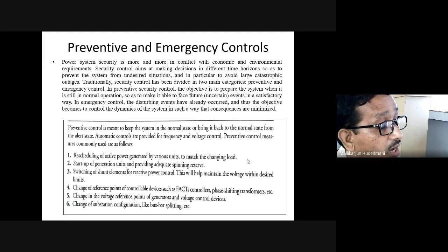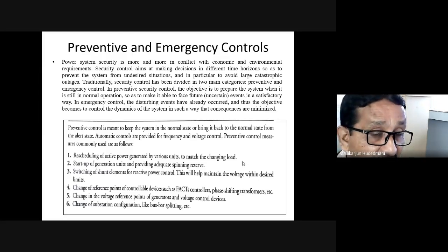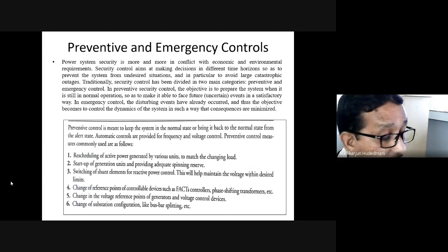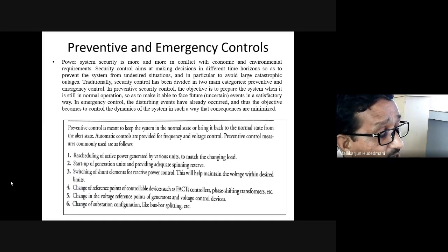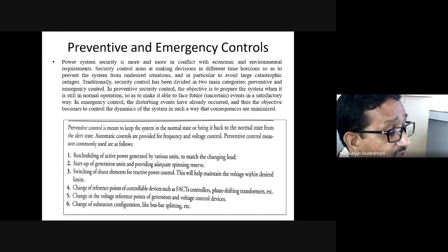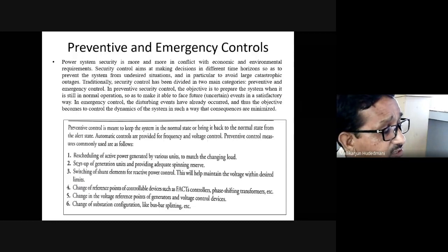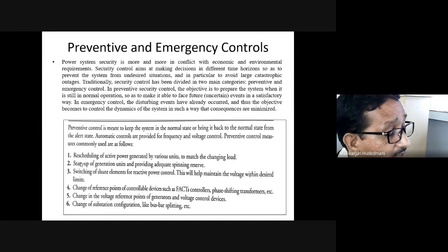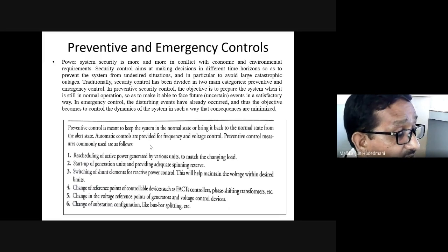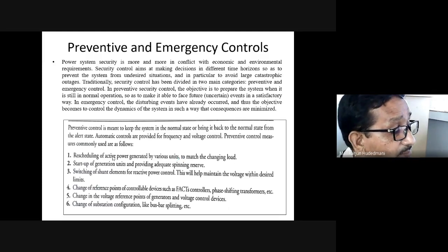Some of the activities are like rescheduling of active power generated by various units to match the changing load. How does the system enter the alert state from the normal? Normal is the state where all the capacity constraints and limits, and equality constraints, are well within range. Certain load variation is occurring, demand is increasing, but the demand is noticed and being served. So rescheduling can help so that it becomes normal again. Changing the set point of a generator is just an action. So, under preventive, load is increasing. Do not let it lead further. Just go back to the generator and change the set point so that it is a new one, and along with the new one, operation is controlled appropriately.